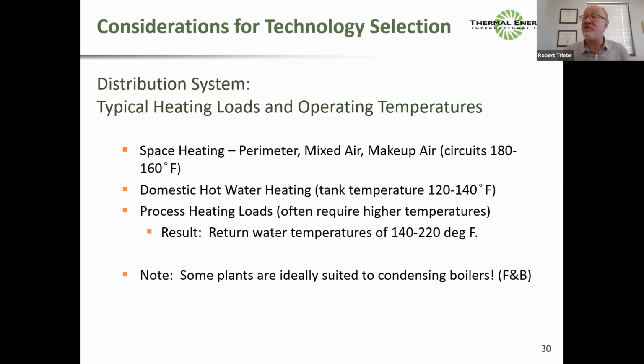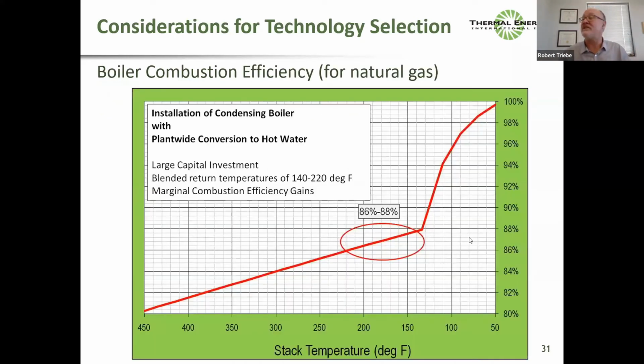And let's talk about a traditional heating system. Let's go into a hospital, a whole bunch of heating circuits, basically the bulk of it's at 180 to 160 F. There's some small colder sinks, but if you put all the users together, the return water temperature, that shouldn't say 220 F, but the return water temperature is going to be 140 to maybe 180 F. So that's the temperature of all the circuits going out. There's no steam out there. It's all liquid circuits, hydronic circuits. They're all coming back to the boiler plant. You put them all together and they're coming back at 140 to 160.